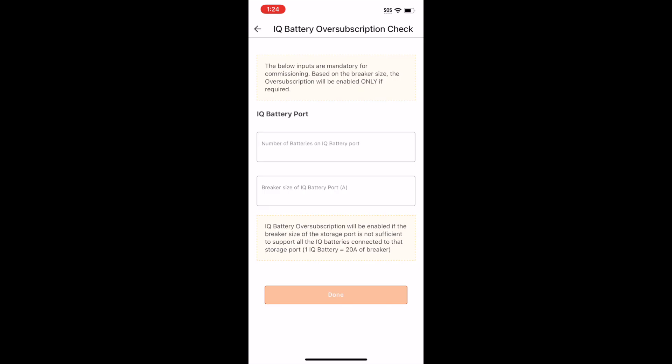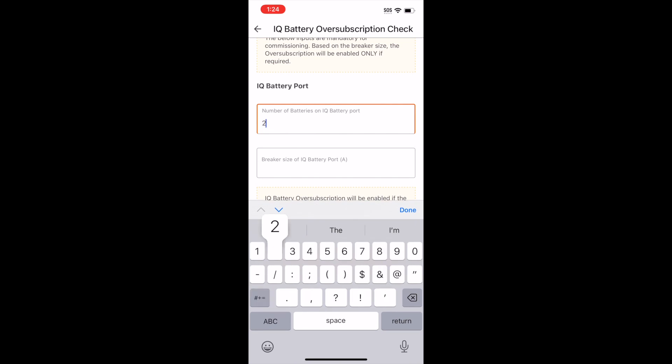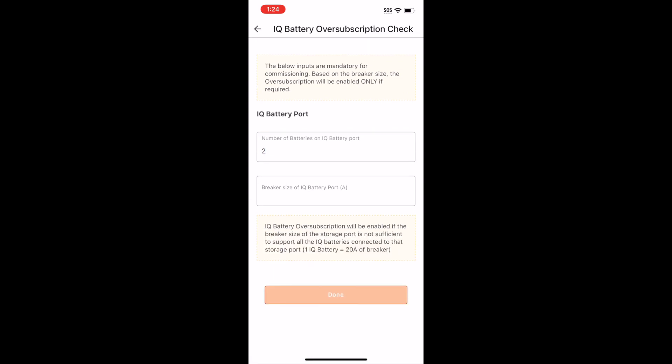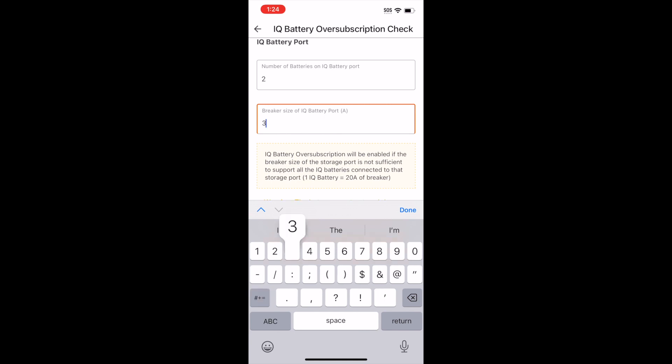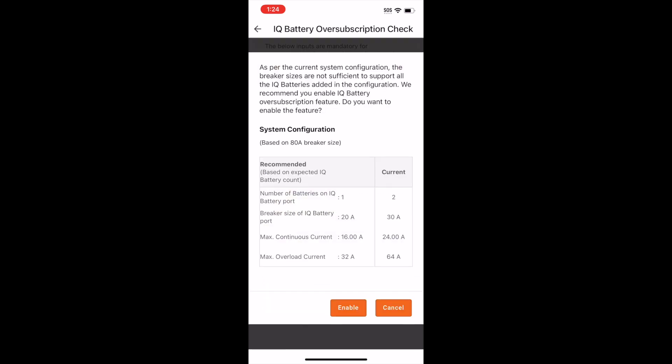Now select IQ Battery Oversubscription Check. The app asks you to specify how many batteries are wired to the IQ System Controller 3 battery input port. For larger battery storage sites, you could have additional batteries wired to the DER input port. This site has two 5P batteries, and due to a site-specific requirement and the interest of showing a battery current limit reduction, we entered a 30 amp battery storage breaker.